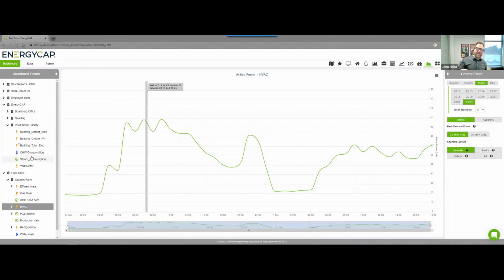The other use case is bringing in temperature. So instead of consumption, it might be temperature reads as part of a chilled water loop, where you can bring in temperature, and then I'll show some functions to do calculated points that can do calculations like delta T, looking at the differences in temperature, or any other type of calculation you might need to create.